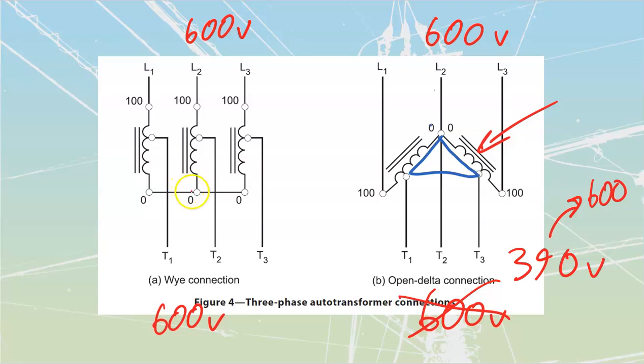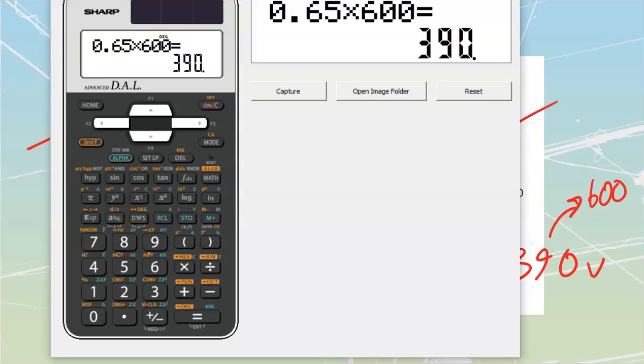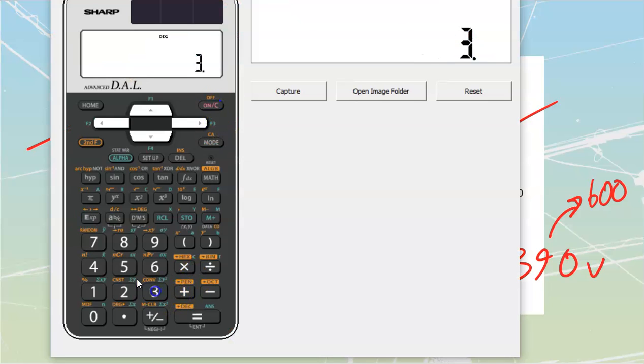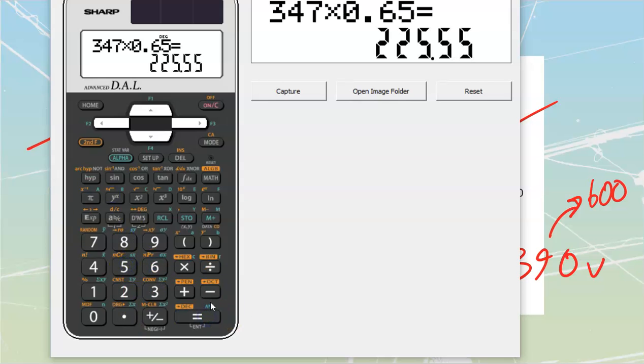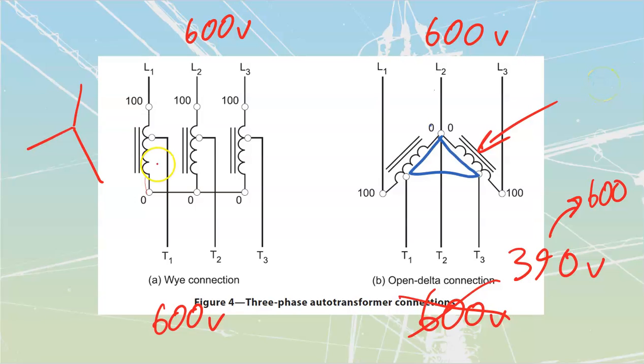If I have this one over here, I'm going to have 600 volts, but when I make that connection, remember that it's connecting those into a Y. So if I'm using the same 600 volt system, but I'm using my 65% taps, now I'm taking 65% of this winding, this 347 volt winding. So I'm going to have 347 times 0.65, which gets me up to a value of 225 volts.